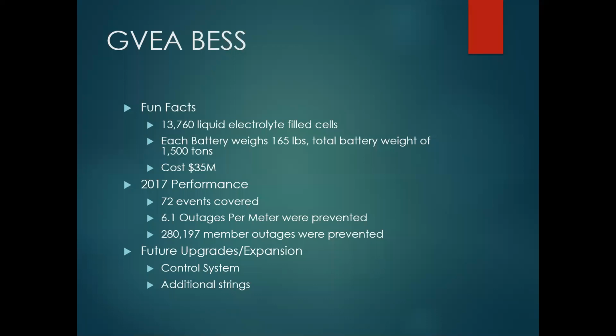We're currently wrapping up what we call a battery monitoring system. The original system came with a sampling system built by a company out of Philadelphia that's now obsolete, so as the equipment failed, it was chuck it in the trash because there are no more, which is unfortunate. That gave us visibility into electrolyte levels, voltage, and temperature of each cell, so you could do some preventative O&M based on what you're seeing. We had to search the whole country to find somebody who could help us gain some of that back. We went with a much more simplified system where we just have temperature and voltage, which through the old system we found out were our key indicators. We'll have visibility at that level within the next month. We're hoping that helps aid the decision process on replacements, additional strings, and maybe preventative O&M.